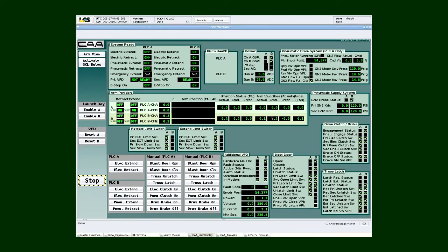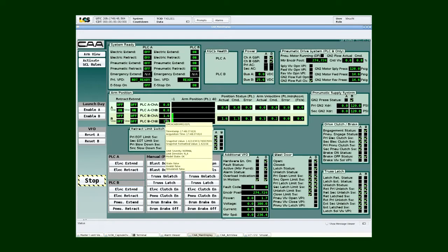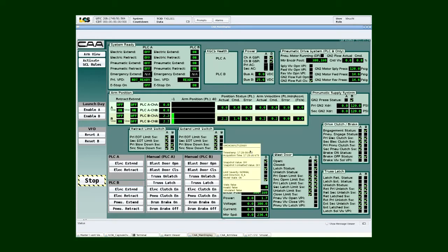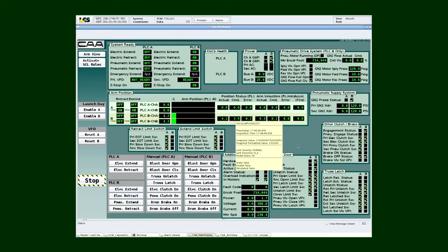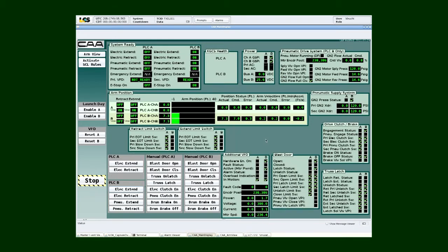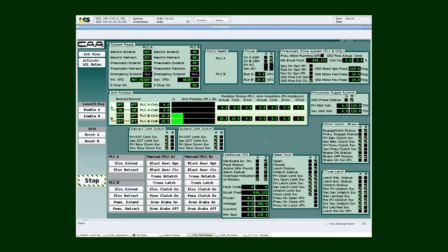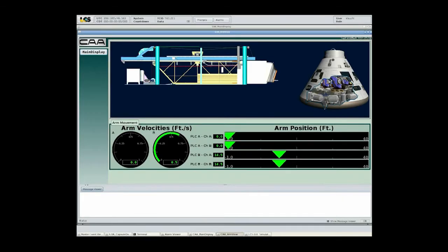As soon as I arm and send my command, if you focus your attention on the center of the screen, you'll notice that PLC B is indicating motion. We're at 2.6 feet per second, approximately 3 feet. You'll also notice that my arm is gaining in speed and acceleration. And if you look at the VFD information, notice that my encoder is counting. I have voltage and current information, and my drive is being powered. And you'll also notice that you have some other information on the screen as far as the drive clutch brake mechanism, the truss latch information, and GN2 supply information. And currently our arm is right about 14 feet right now in position.